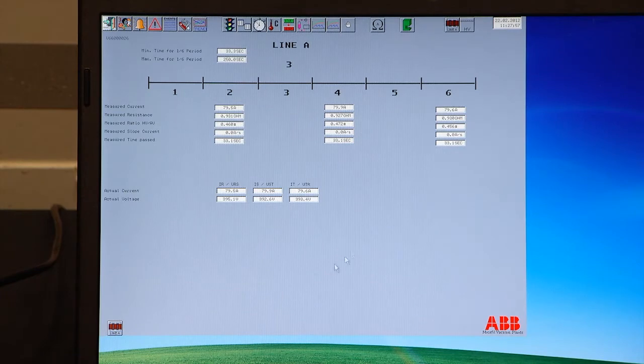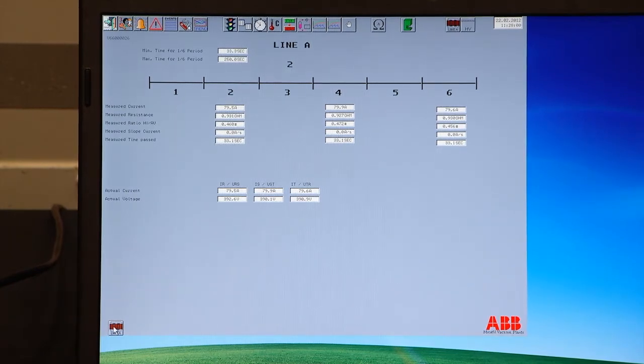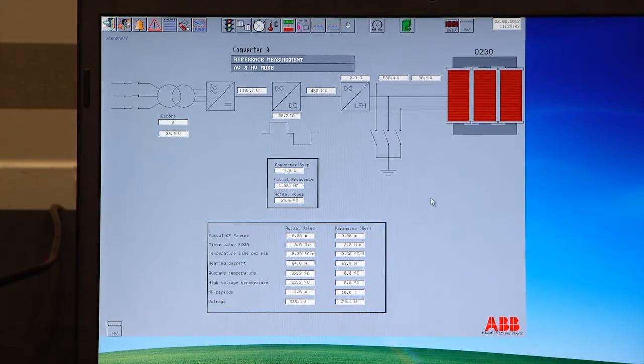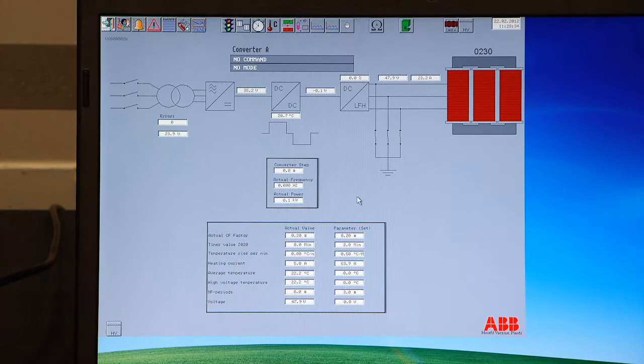Now he has performed the measurement in all 6 steps. We are back in the average mode. We are running at 1 hertz. And now we are performing something that we call demagnetization. Because we have a very uneven balance of the magnetism in the transformer, we are running a sequence of 3-phase heating or 3-phase current to equalize, to balance out the magnetism in the core.